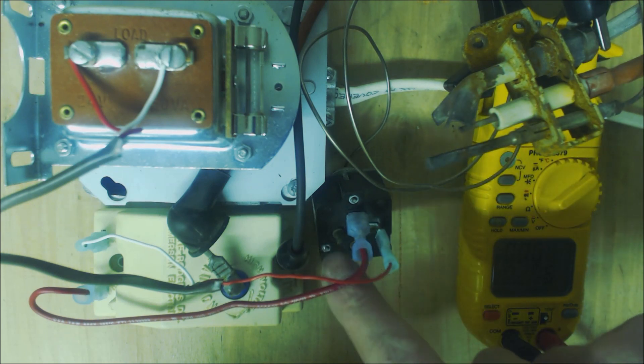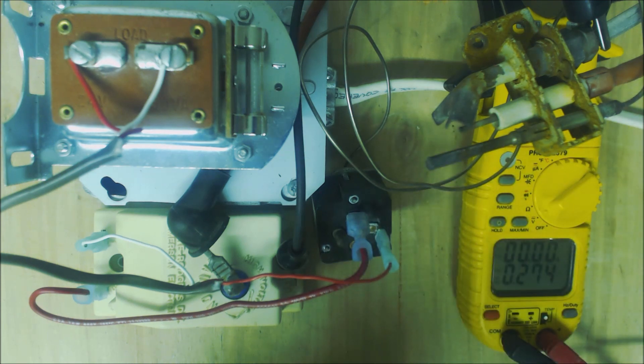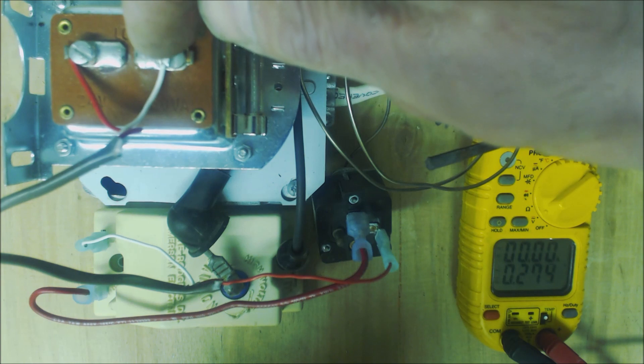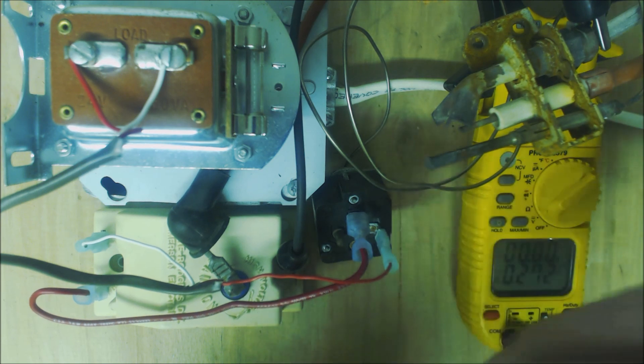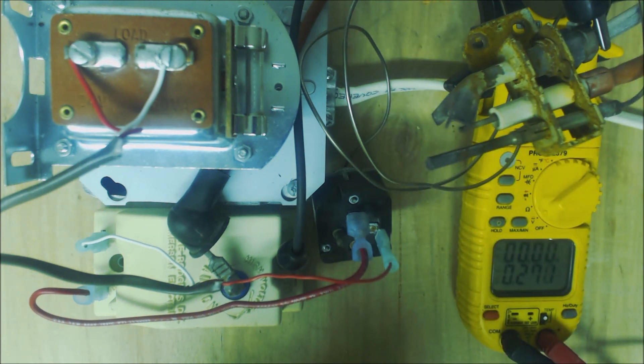You have a wire coming from here to the main gas valve and a common coming from here to the main gas valve. So you'll have your pilot lit, then you're going to stop sparking and send 24 volts to the main gas valve.